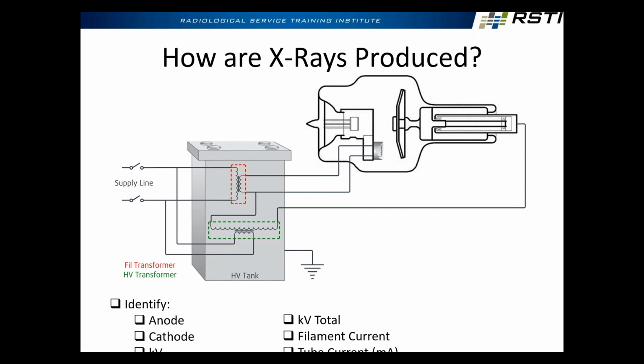All right. So that leaves us with a nice little target assembly here that's going to be rotating at one of two speeds, either 3,450 RPM for low speed or 10,000 RPM for high speed. High speed is more expensive because I have to add other stuff. I have to have a braking circuit. I have to have all the additional gear to take the stator frequency from 60 hertz up to 180 hertz. But it allows me to do much longer exposures. So if I could do maybe a 0.3 second exposure at a certain kV and mA in low speed, I might be able to do, instead of 0.3 seconds, 3 full seconds in high speed.